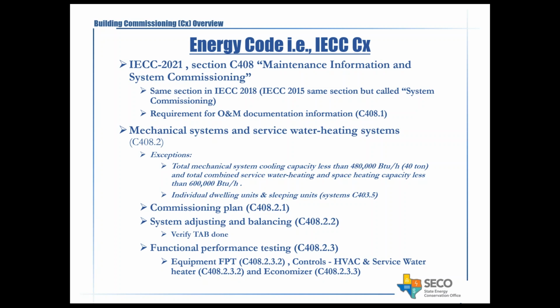So if you have a building that does not have the system capacity for HVAC and the plumbing and heating systems at or above what is identified there, you're not required to have commissioning done for that aspect of it. The code requires a commissioning plan. It requires system adjusting and balancing, making sure verification of TAB has been done, and the sections that I'm identifying are the sections in the code that specifically talk about these topics and go into more detail. IECC commissioning requires functional testing of controls in HVAC, service water heating, and any economizers. The functional performance test is an important aspect of the overall commissioning process, which typically happens in the construction phase.